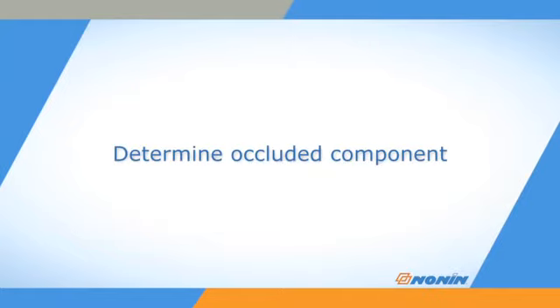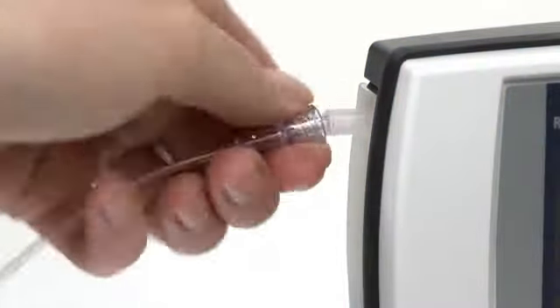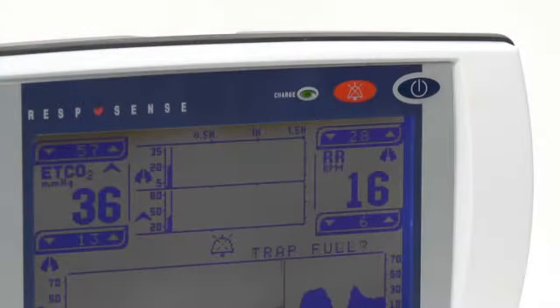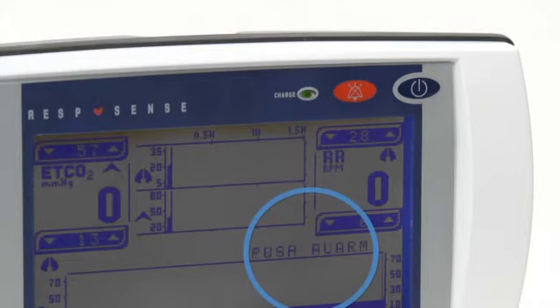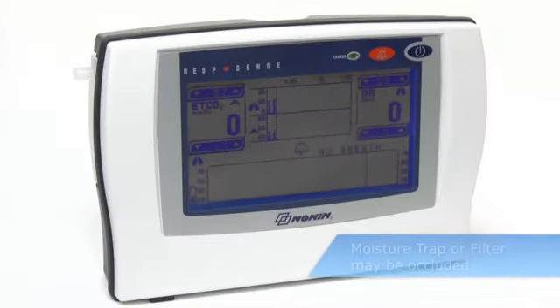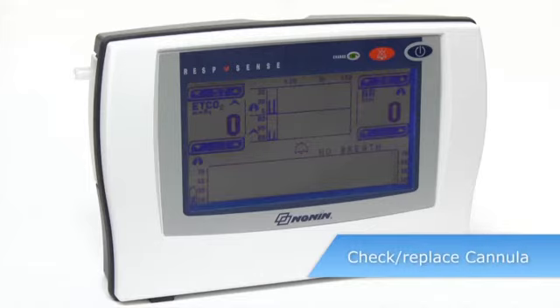You can determine if the occlusion is in the cannula or the filter and moisture trap combination. Disconnect the cannula and press the Alarm Reset button. The monitor will start running. If the unit alarms and displays the trap full push alarm within 15 seconds, the moisture trap or filter may be occluded and should be replaced. If the monitor runs more than 15 seconds without an alarm, the cannula may be occluded. Check and replace the cannula as required.